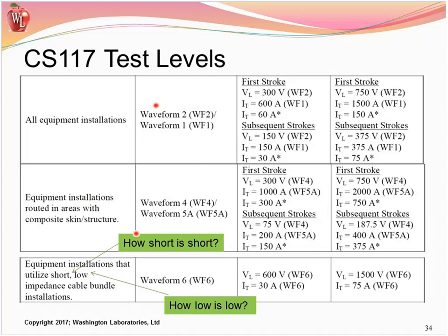Now these are just a few of the extracted levels out of the standard, but here's a concern. How short is short? The item says for short cables it doesn't apply. Well, short might be 3 meters to some people and 50 centimeters to the next person. And how low is low? If you just don't know these values, something has to be determined. I suggest your test procedure take care of defining this, so you can get agreement between you and the end user as to what it will be and what the compliance parameters are.